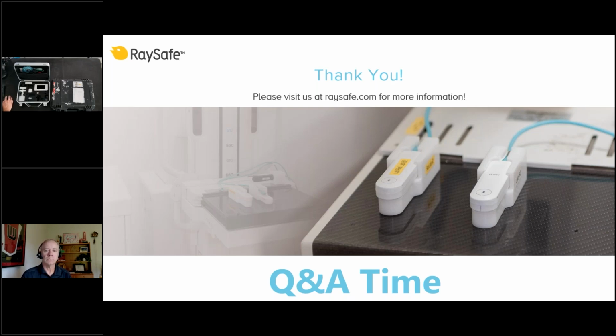Okay, wonderful. Thanks, Ed. In your documentation, you mentioned minimum manual settings. Can you explain what enables that? I think it's the robust algorithms in the sensor itself, the robust design. We have a wide range. We can measure kVp with a wide range of filtration in the RF sensor, and also the MAM sensor. You do have to choose your target filter combination if you're measuring kVp on your MAM sensor, but if you're just measuring dose or HVL, you don't need to change. So we have some very brilliant people over at RaySafe in Sweden who designed these things, and robust algorithms make them very versatile and very user-friendly.